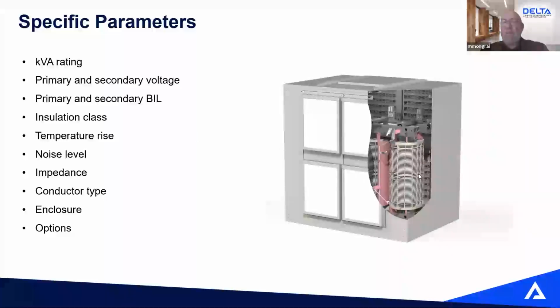The temperature rise has a big impact on the transformer size. So usually power transformers are 150 rise, but you can have a lower temperature rise, 115 or 80 rise. Do I need something with a lower noise level? There's certain standards that we have to meet, but if your transformer is located close to an occupied area, you may want to consider having a lower noise transformer.